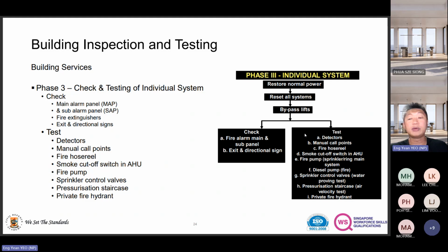Eventually what we need to do is really test out each system individually. Do they give the reading we want? Do they give the flow rate we want, especially on the hydrant side? Because hydrants usually don't have any pumps - it's straight from the pressure of the main supply, and there's a big valve that's usually only opened during testing.